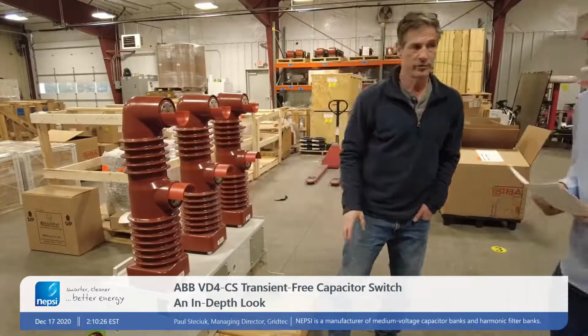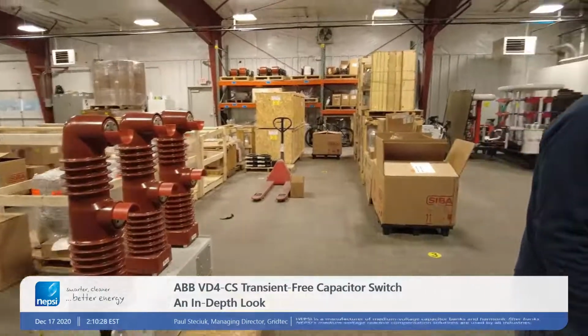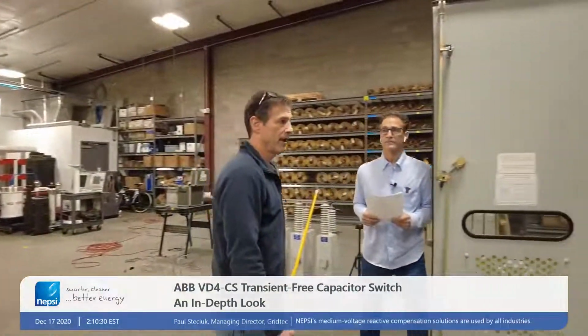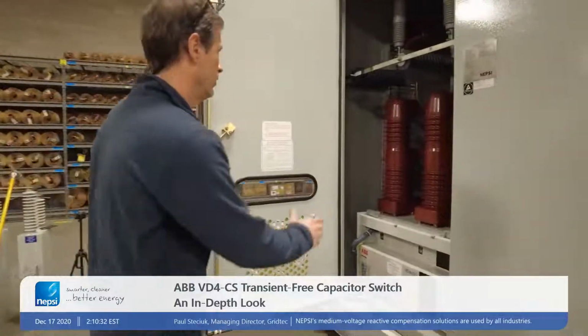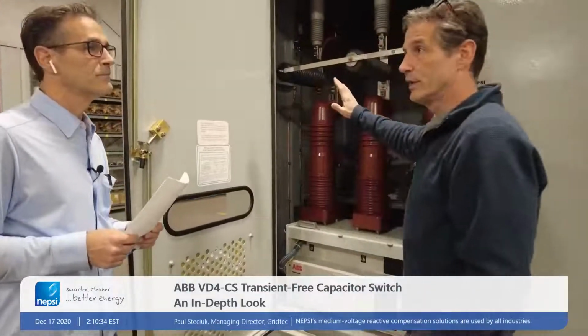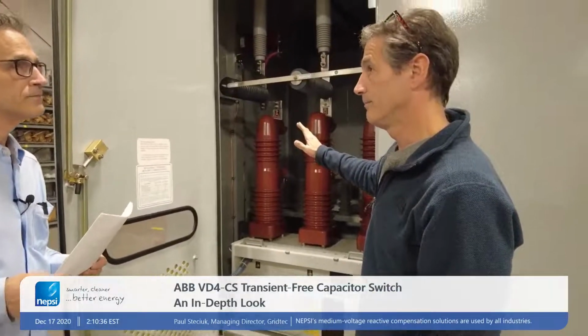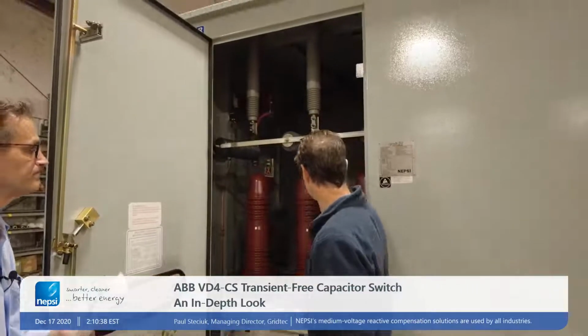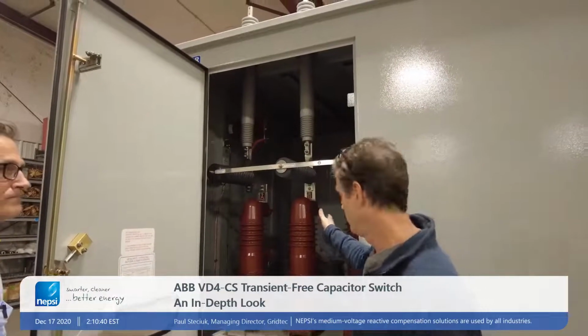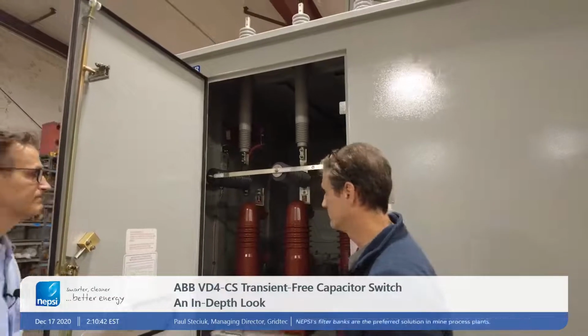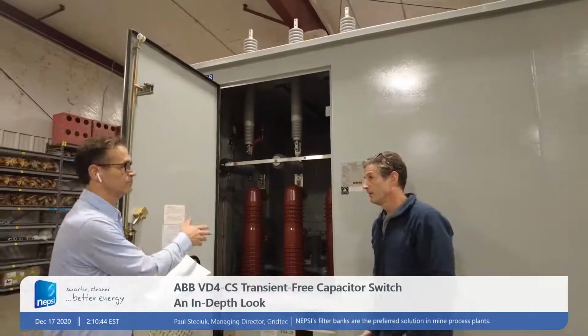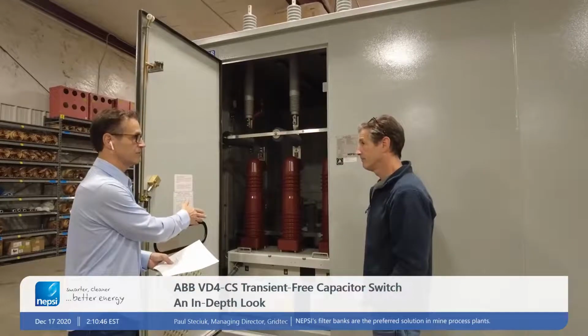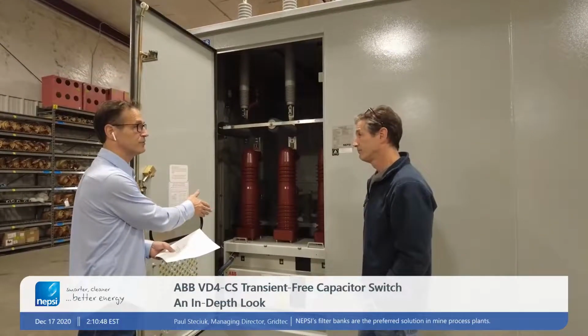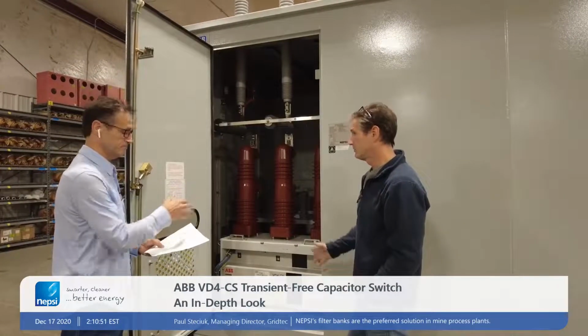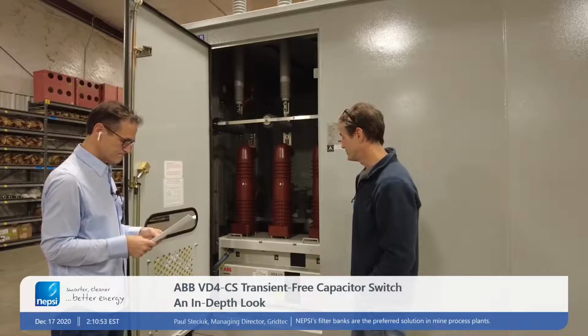The other thing we do, if it's a super cold environment, say going up into northern Canada, is insulate the whole enclosure on the inside as a second line of defense, and heat the internal compartment where the VD4 is located. We actually put a permissive into the control circuit to prevent operation under a cold temperature environment, right? Correct, that's the under-temperature protective feature.